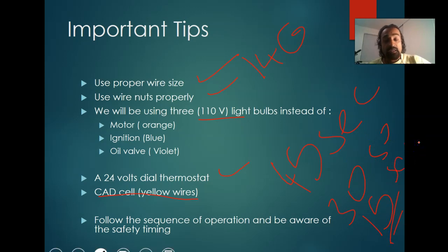We can do better. So 15 seconds is the new safety timing in Massachusetts. It could be more somewhere else. And if you think about it, that's enough time to activate fire. What happens? So 15 seconds, no fire, it will shut off.